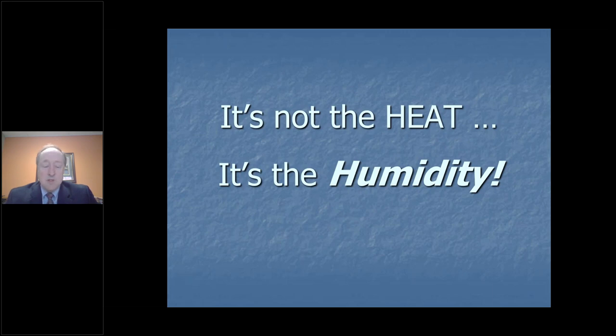The problem that I see with so many of the designers is that we are so reliant on software. We plug in the design day and it spits out numbers, and it tells us I need this particular amount of latent load and this sensible load. I can do this with X number of tons. And then you never really even plot that out on the chart to see if it's really going to work. So I would encourage all of you designers to always plot out the process on a chart to make certain that what you're designing is really going to work.